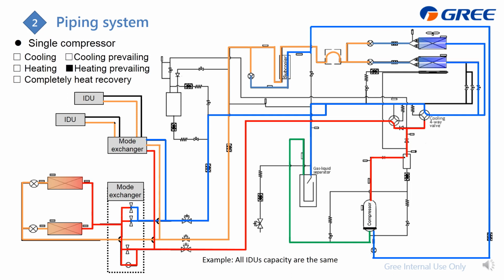Next, we'll go to the heating prevailing mode. That means if there are 2 indoor units requiring heating, and 1 requiring cooling. And here we just send the liquid refrigerant to this indoor unit, and then make it get expanded and become low pressure and temperature to absorb heat from the indoor room, and then become gas and flow back to the mode exchanger.